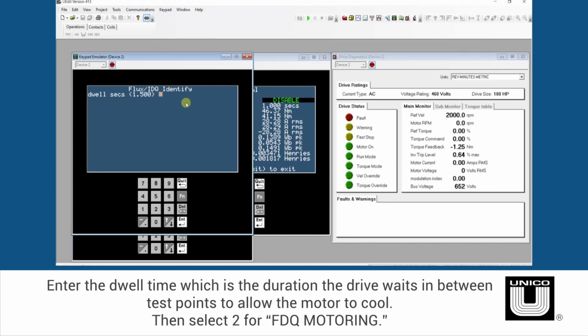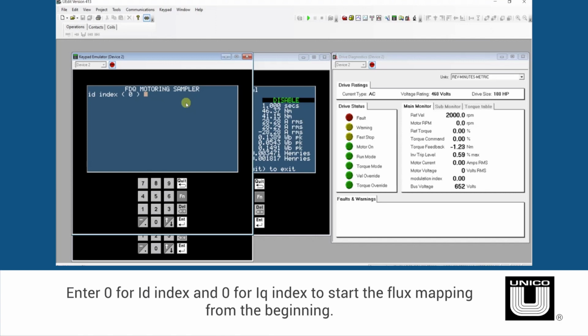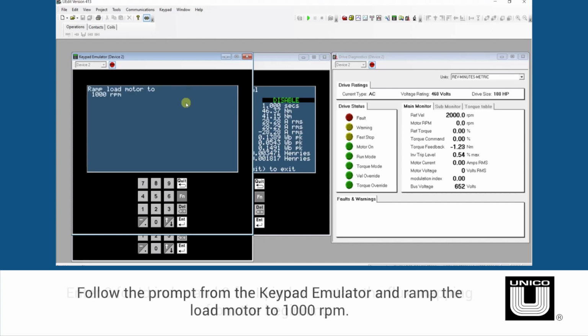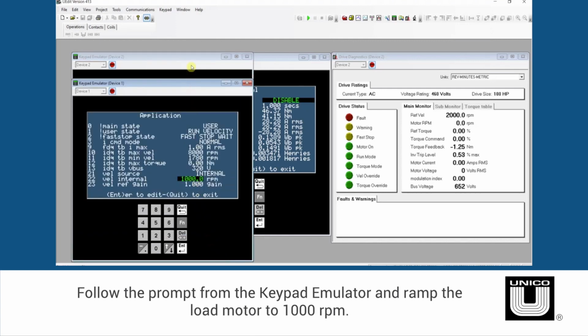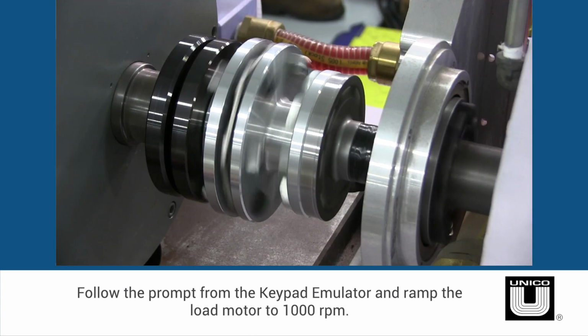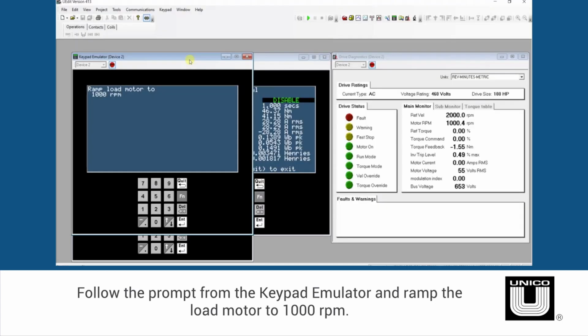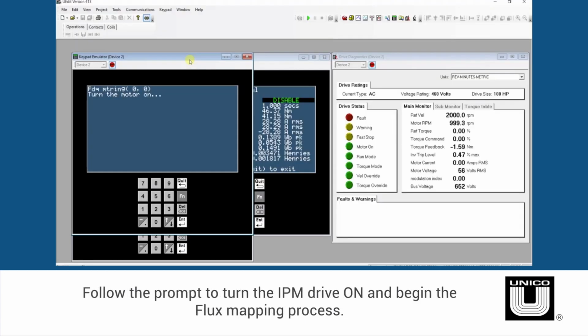Enter the dwell time, which is the duration the drive waits in between test points to allow the motor to cool. Then select 2 for FDQ motoring. Enter 0 for ID index and 0 for IQ index to start the flux mapping from the beginning. Follow the prompt from the keypad emulator and ramp the load motor to 1000 RPM. Again, follow the prompt to turn the IPM drive on and begin the flux mapping process.